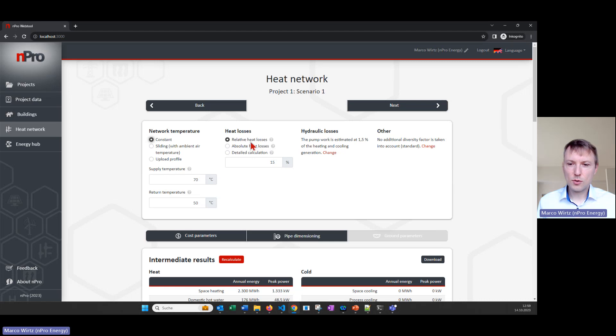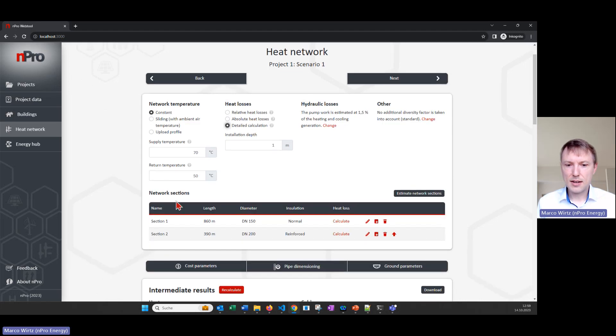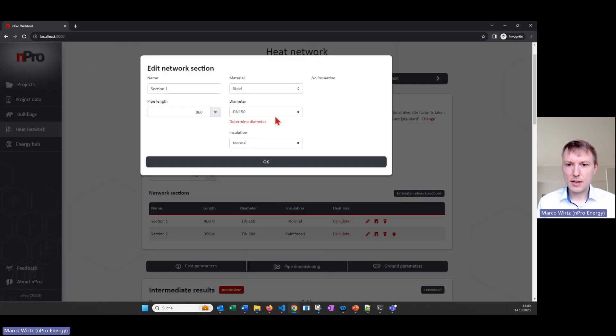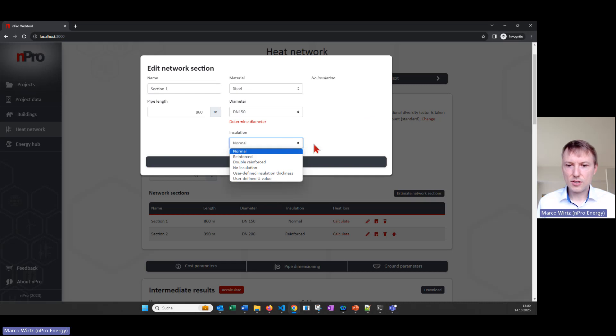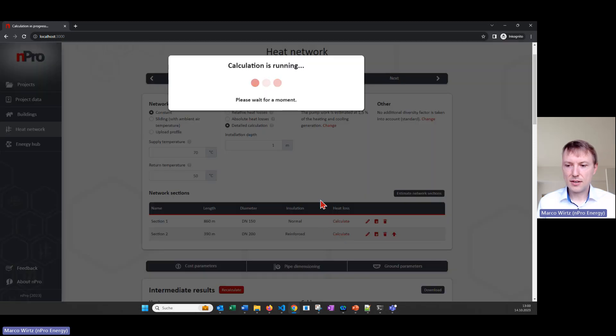We can define the losses — this can be very simple with just a loss parameter, but we can also have a more detailed calculation. If I click on 'Detailed Calculation' then we get a list of network sections, and here we can really define what the sections of the network are, what the branches are, the diameter, and also the material and insulation thickness. Based on this we then have a more detailed heat loss calculation.